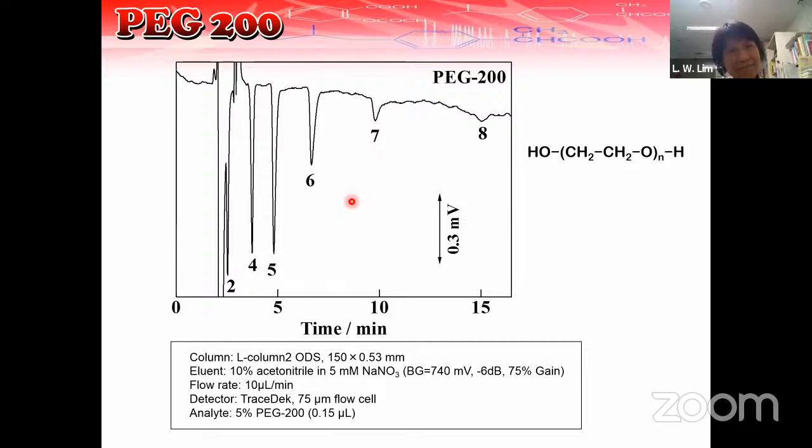So that's why when we make a column or when you use a system, you have to make sure the repeatability, I mean the reproducibility, is important. Yeah? If you inject 3 times, same sample, everything the same, but your peaks, your chromatogram, is different, that means something is so wrong. Yeah.